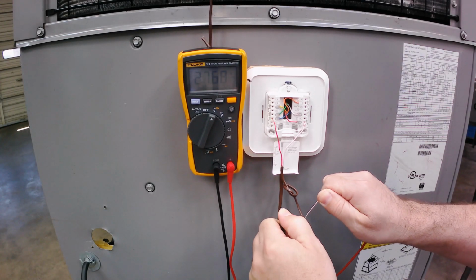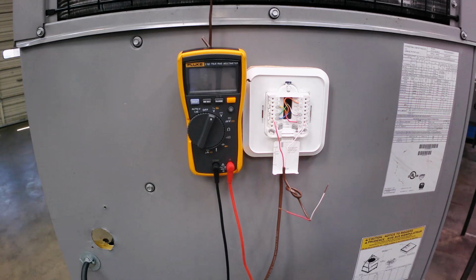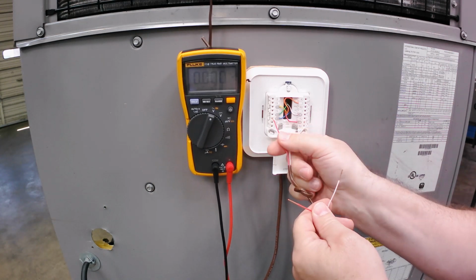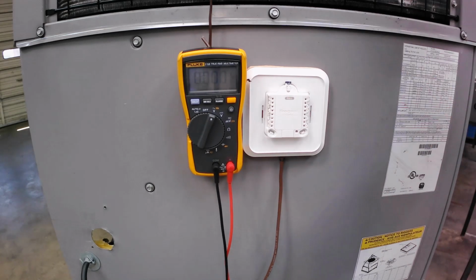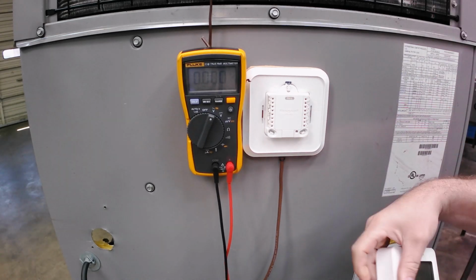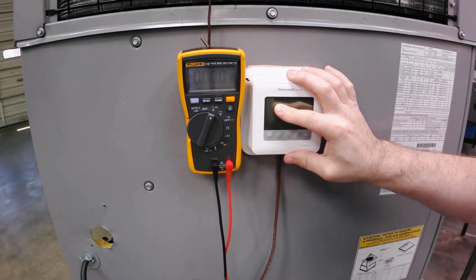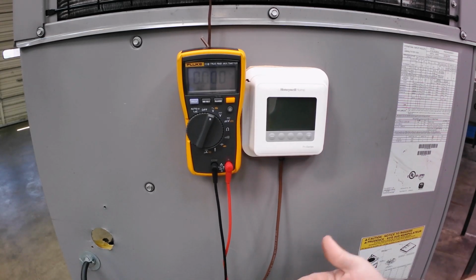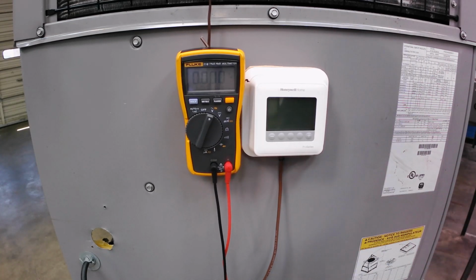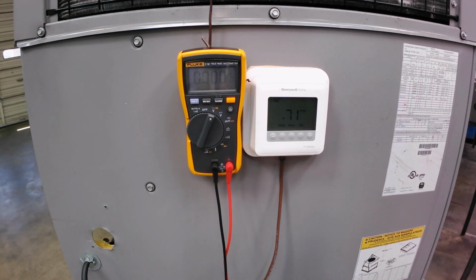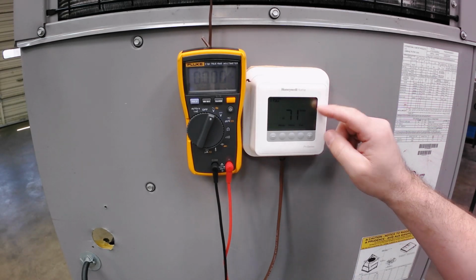If you can prove power into the thermostat, that is a starting point. That means this thermostat has the required power to power it as a load, and that R is going to be distributed out through the system once this thermostat calls for heating, cooling, fan, reversing valve, or whatever. So the power check is always, to me, first and foremost if you have any doubts.